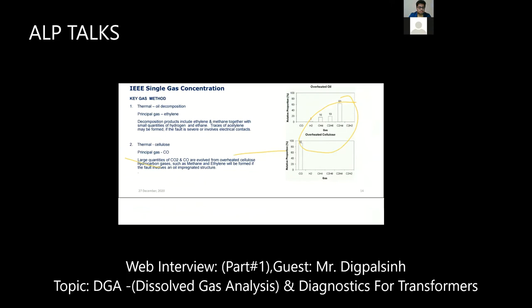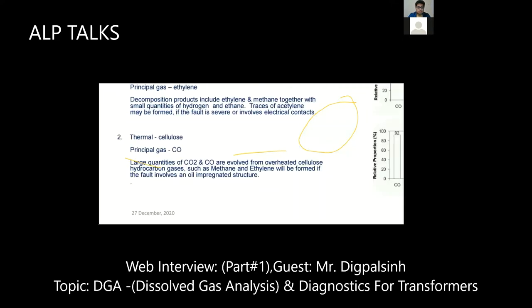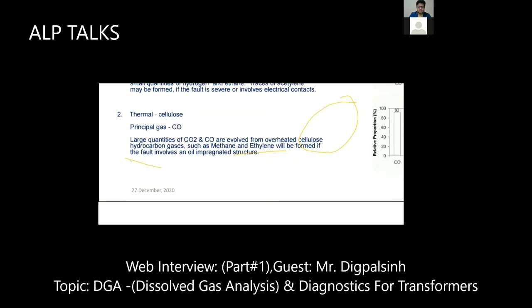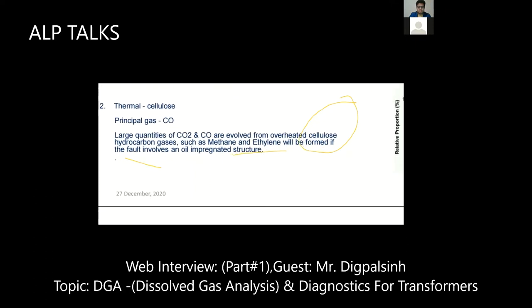Second, thermal fault in cellulose. For the cellulose, the main principal gas is carbon monoxide. When you do DGA of the mineral oil, if you find carbon monoxide goes beyond its defined limit, and you end with a large quantity of carbon dioxide, then you can say it is a thermal fault inside your cellulose material. This is because of the overheating of the cellulose material. In this case, methane and ethylene will be found.